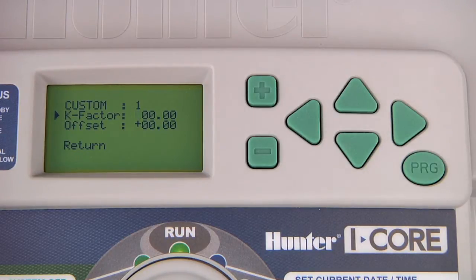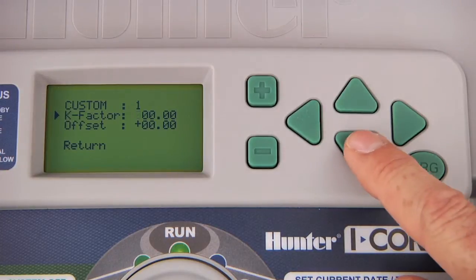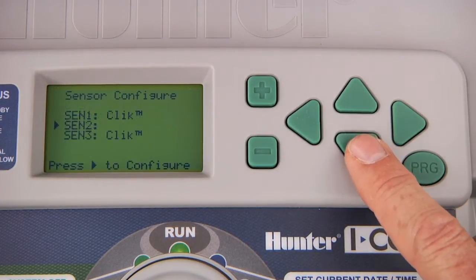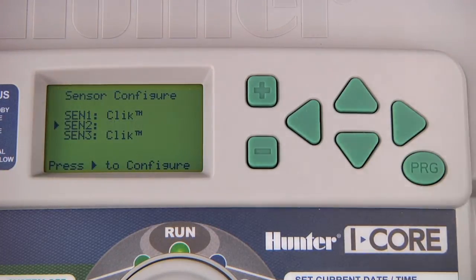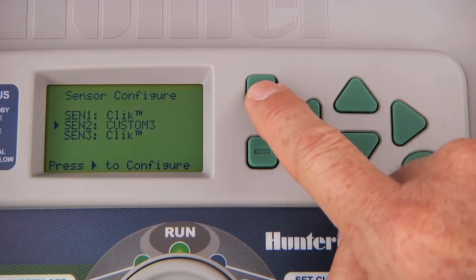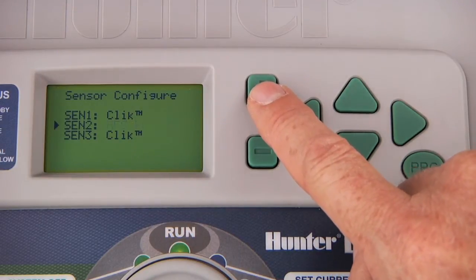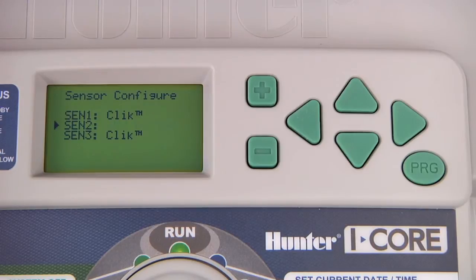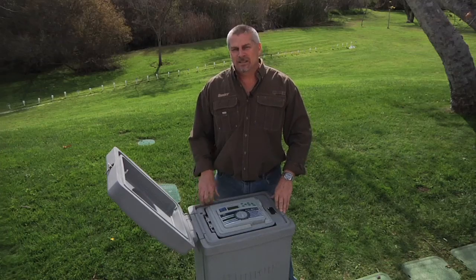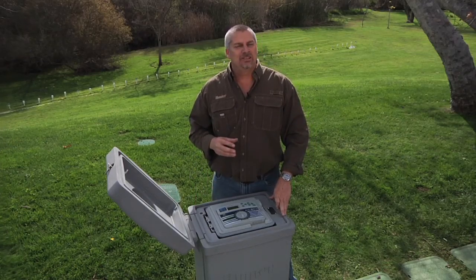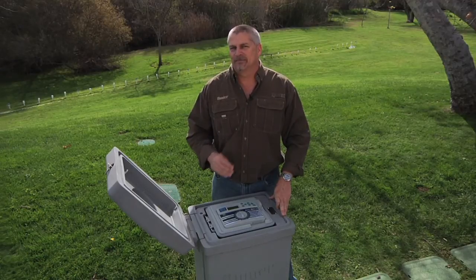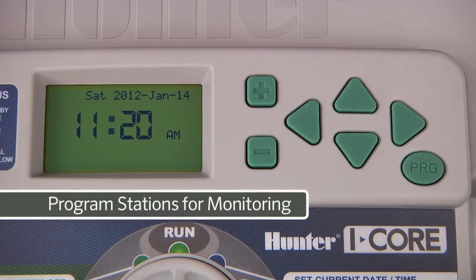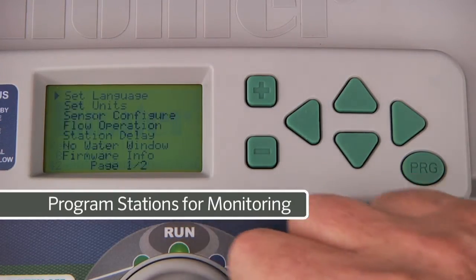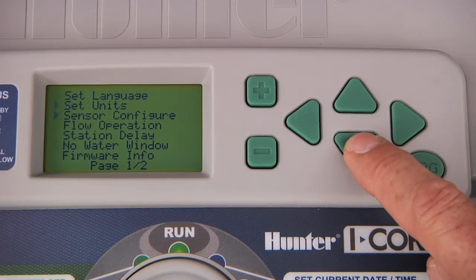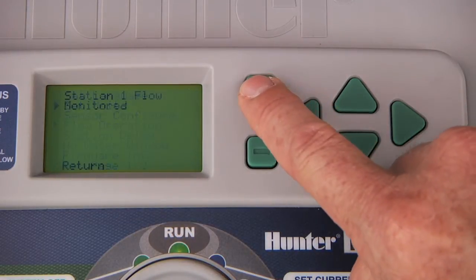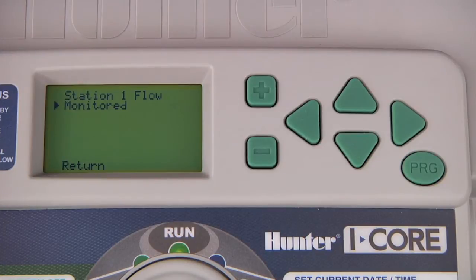To go back to the sensor configuration screen, press the down arrow button until you reach Return. To stick to our example, we'll configure the second sensor input as a Hunter flow sensor with a 1-inch Schedule 40 fitting. Once the sensor is configured, we'll need to tell each station how to respond to that sensor. To set the response for our flow sensor, we need to go to Advanced Features and press the down arrow button to select Flow Operation and press the plus button to access it.